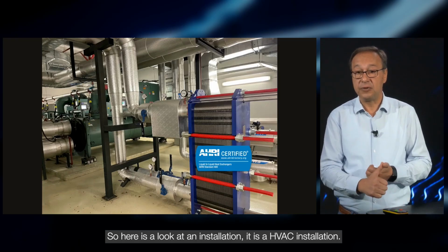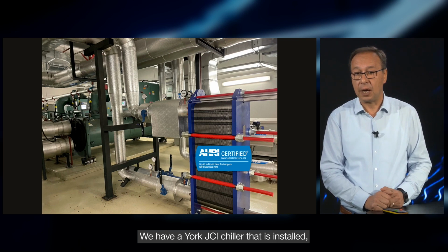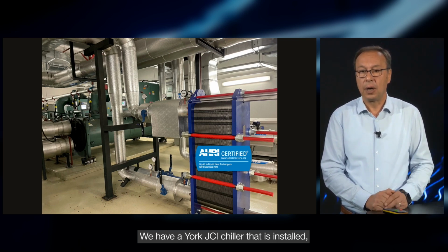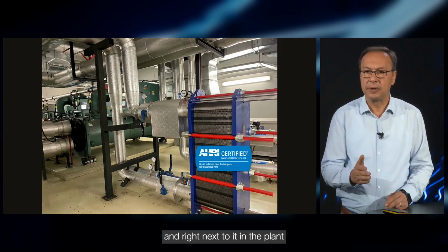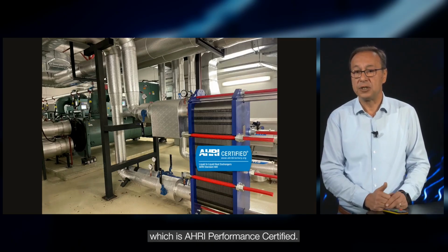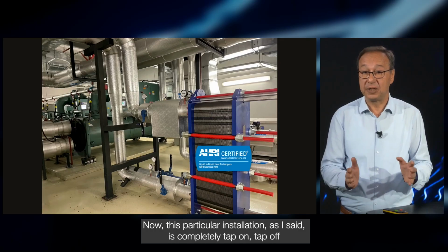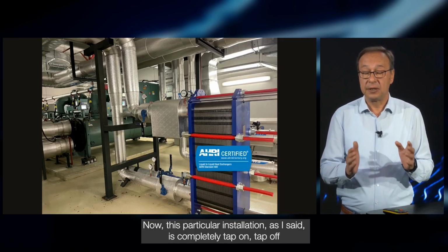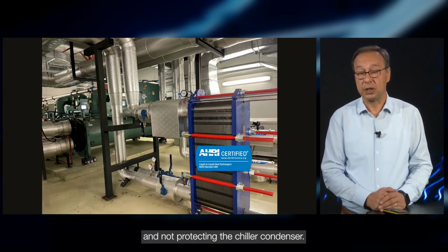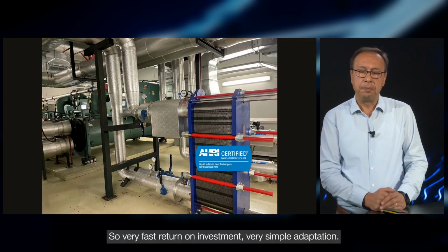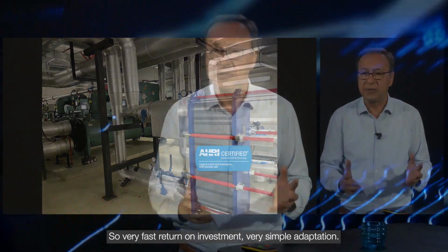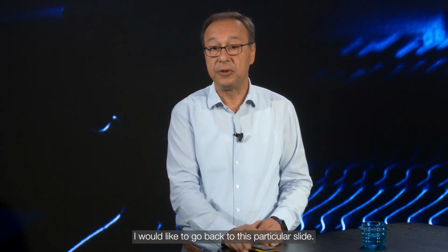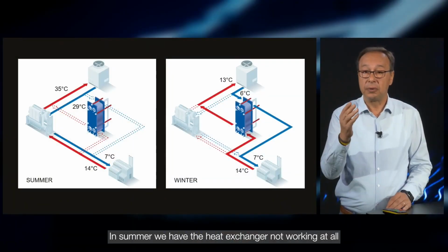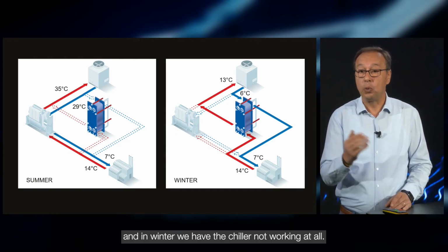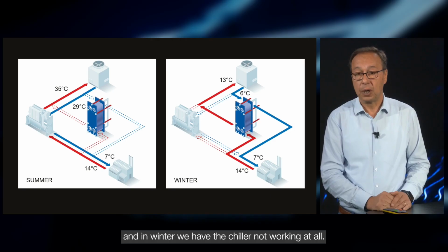Here is a look at an installation. It is an HVAC installation. We have a JCI York chiller installed, and right next to it, in the plant, we have a gasketed plate heat exchanger, which is AHRI performance certified. This particular installation is completely tap on, tap off, and not protecting the chiller condenser. So, a very fast return on investment and a very simple adaptation. Going back to this slide: in summer the heat exchanger is not working at all, and in winter the chiller is not working at all. So the savings are there.